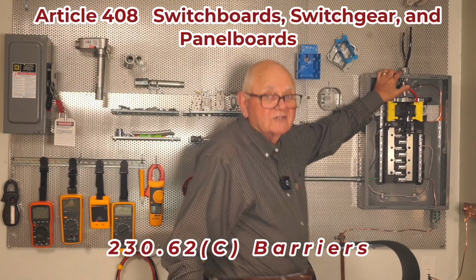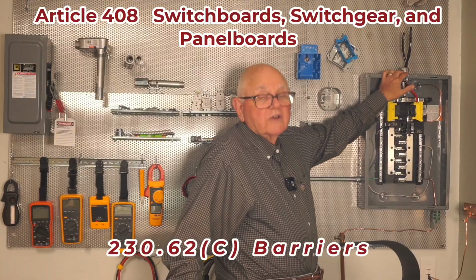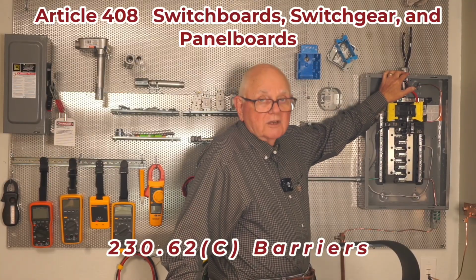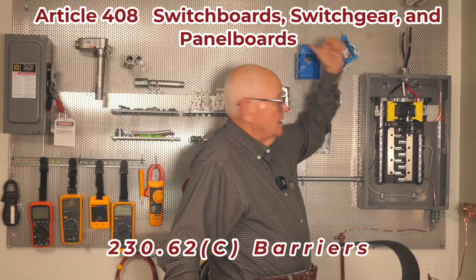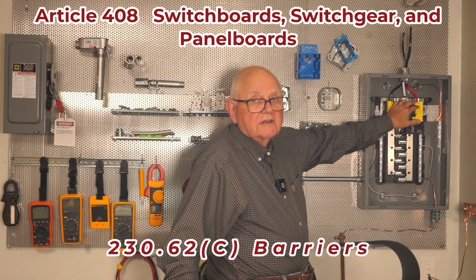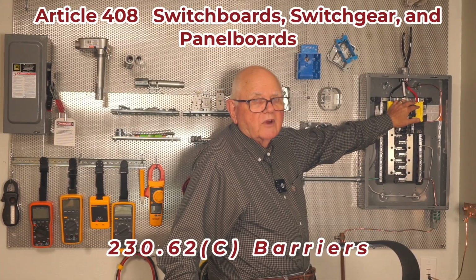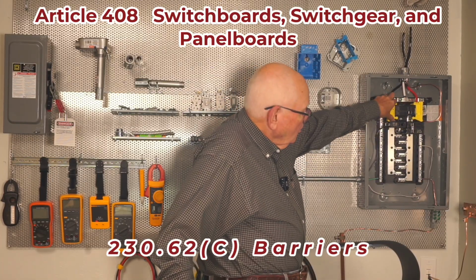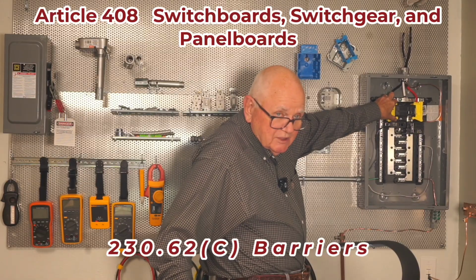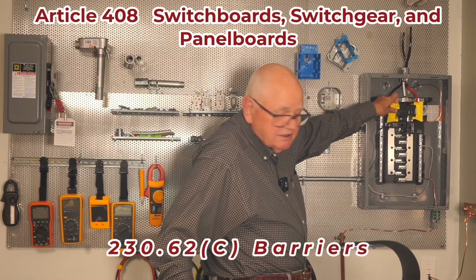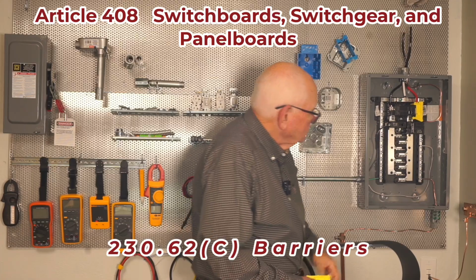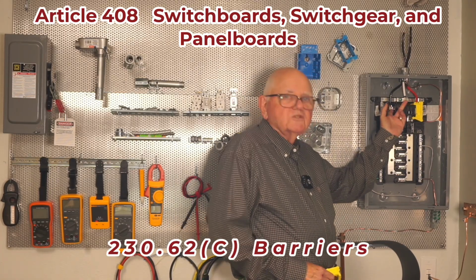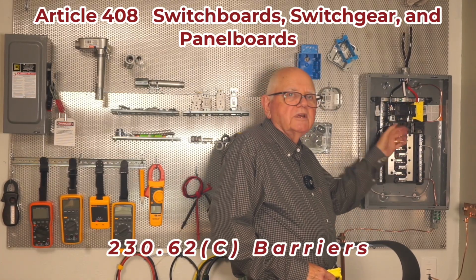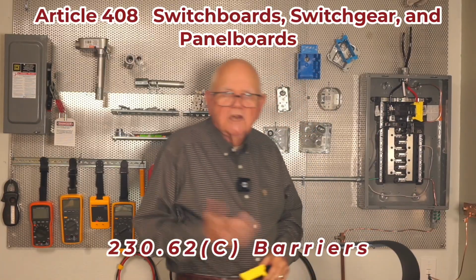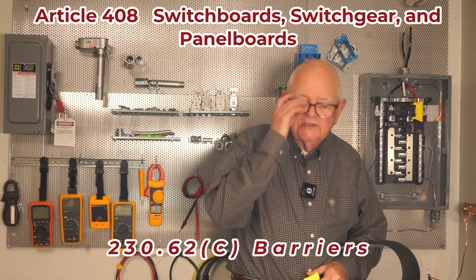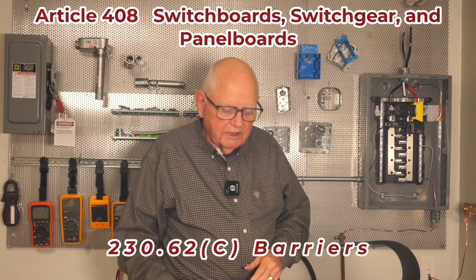the incoming conductors. I am required to have overcurrent protection on a panel board. That overcurrent protection can either be at the source of supply or right down here inside the panel board with this main breaker. So when we purchase this panel board, it comes with these barriers in it, and 230.62(C) once again said that these barriers have to be installed over those main terminals. So that way when I'm in here working, I don't inadvertently touch those main terminals and injure myself. So I think that's a pretty good requirement, been in the code for a little bit.